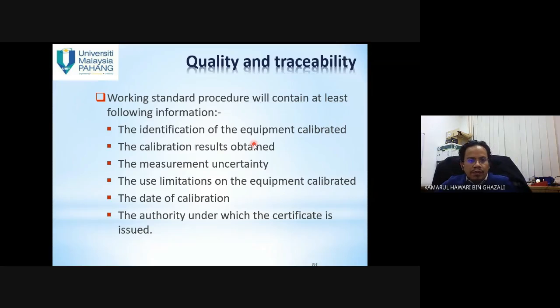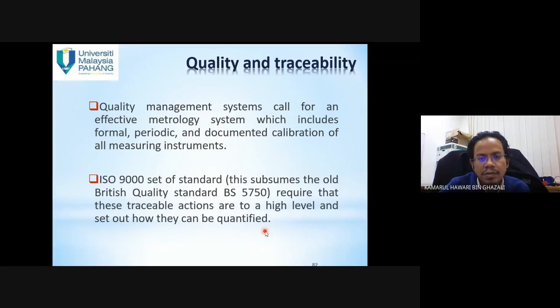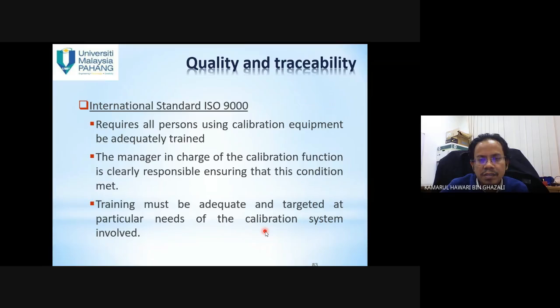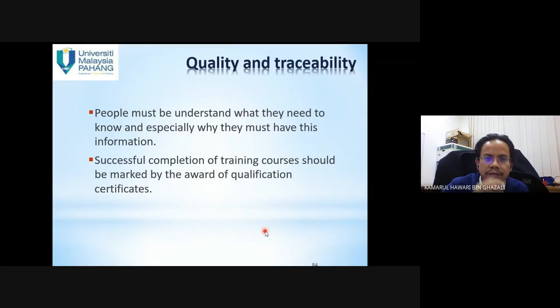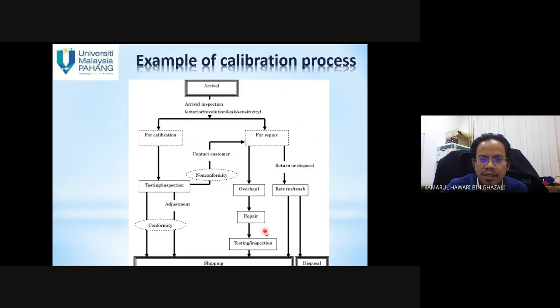Working standard procedure will contain at least the following information: identification, calibration, measurement, use limitation, date of calibration, and the authority under which the certificate is issued. Okay, so this is the quality and traceability, the ISO 9000 set of standards. This is the standard. This standard has been developed, used and recognized internationally. So you don't have to worry about the standard commission for the standard. People must understand what they need. Successful completion of a training course should be marked by the award of a qualification certificate. So this is an example of a calibration process. Arrival, calibration, testing, non-conformity, contact customer for repair, shipping, kalau rosak, disposal.